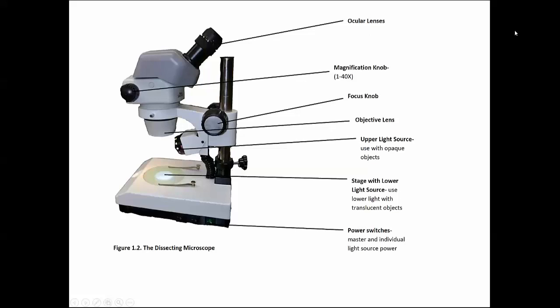The dissecting scopes tend to go up to about 40x total magnification and that's where the compound scopes pick up. So they start at 40 and go up to about 400. There's a focus knob, there's a light source, there's usually a rheostat. There's usually more than one light source on these, one from above for looking at 3D objects like your hand or a bug. There is a light from beneath to look through water samples or slides.